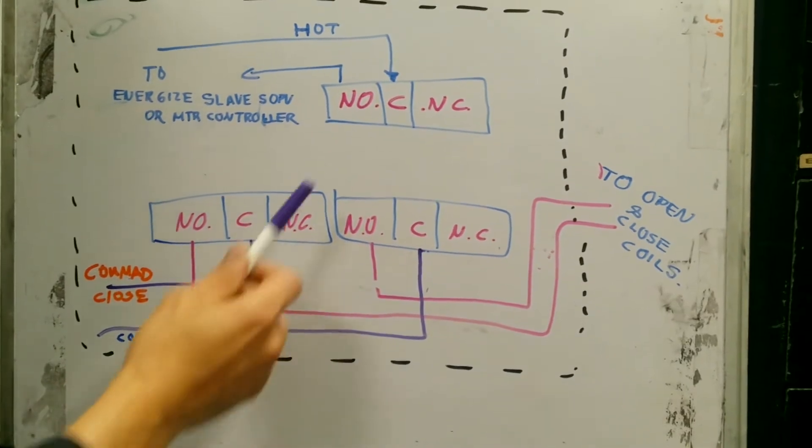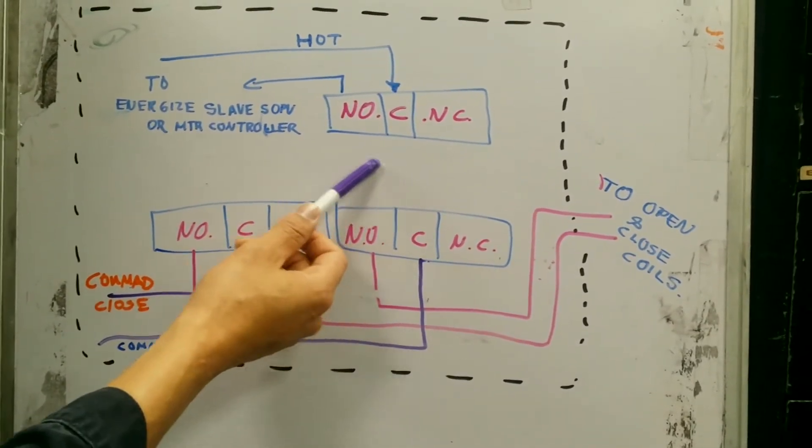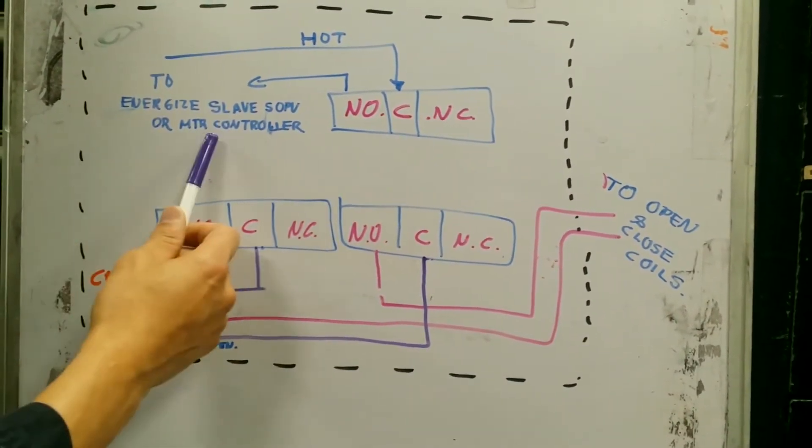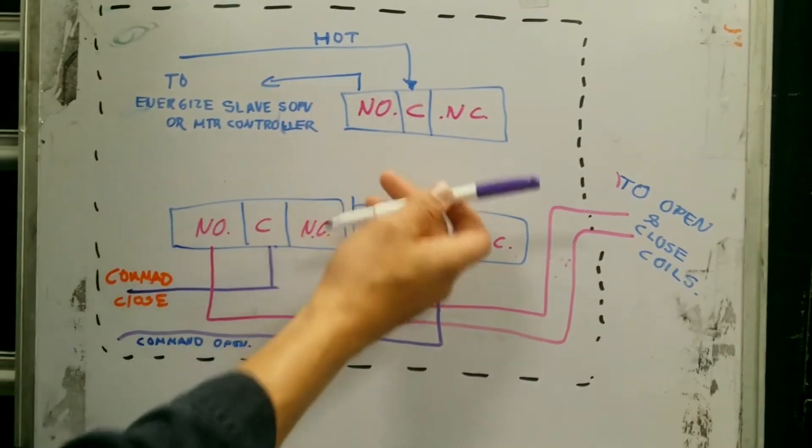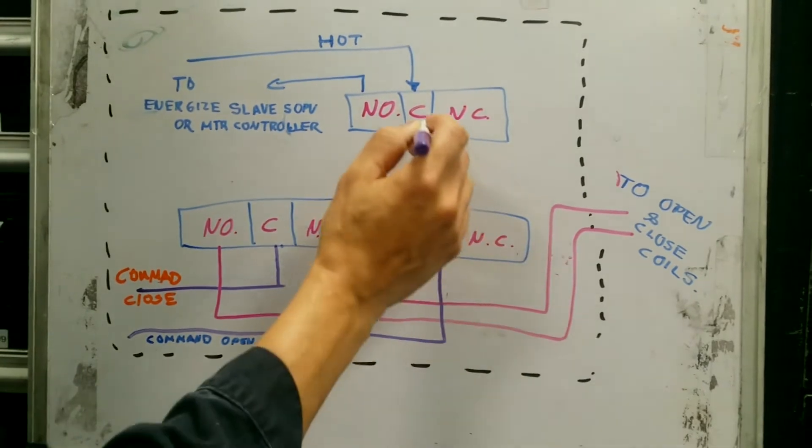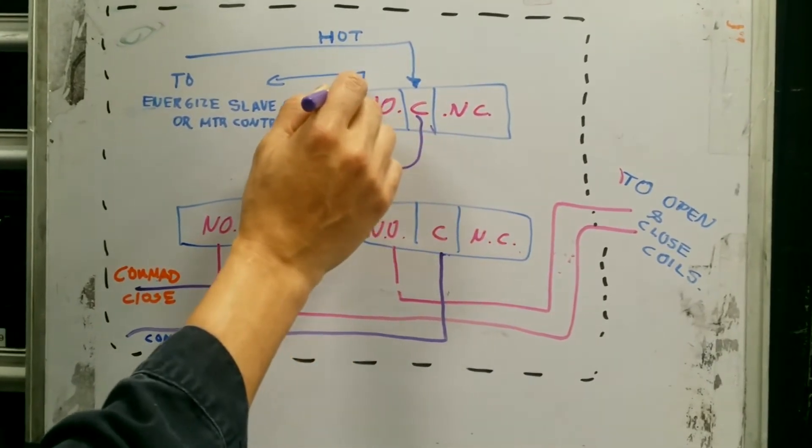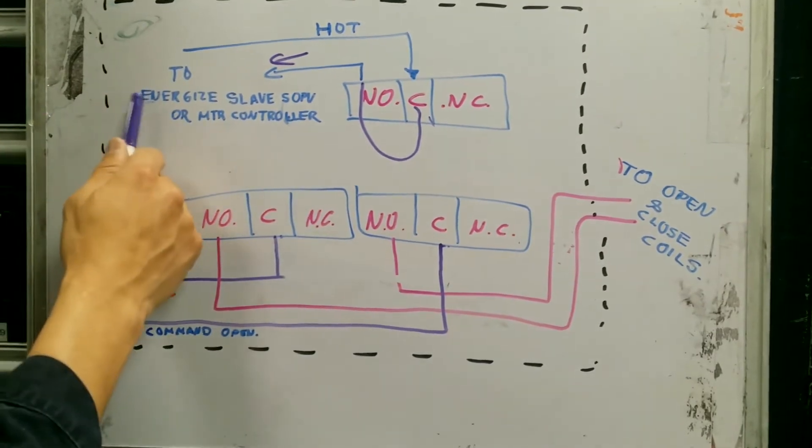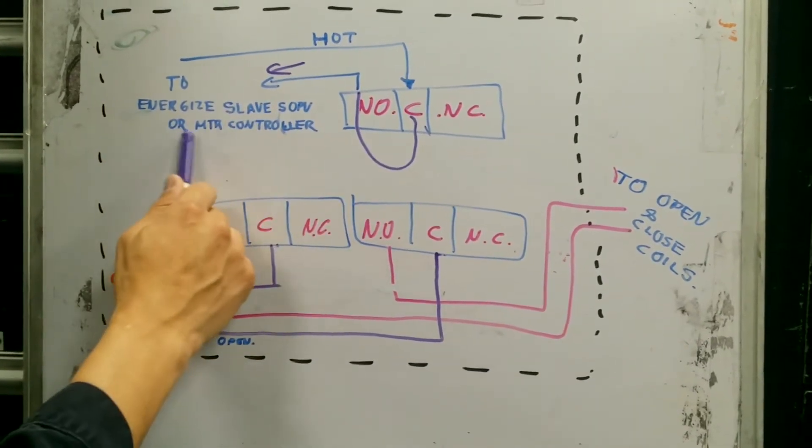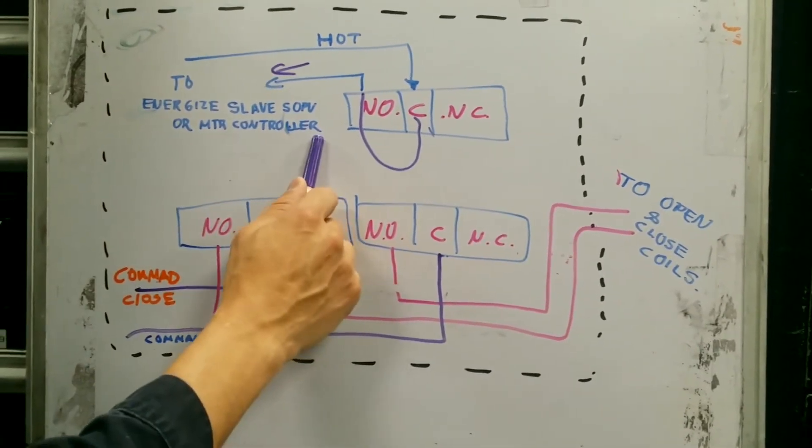A moment ago, I said that an SOPV valve will energize another valve or a controller, and pretty much how it works is there will be a hot line coming in, and then when the valve opens, it will close a set of switches to put power or command to either energize an SOPV valve or for the motor controller to start the motor.